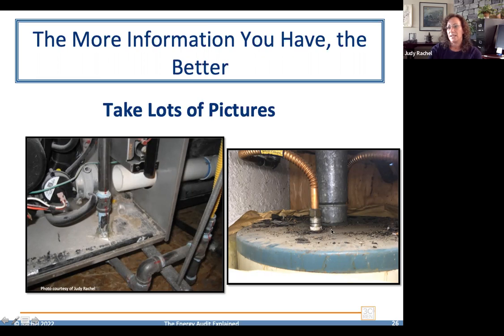And now we've just basically got a great big gas leak going on because we've got this water heater that is firing with no fire. So there's just gas, and it's never going to satisfy because it's never going to heat up to the point at which the thermocouple says, oh, we're hot enough, we're satisfied. So that gas is just going to continue to leak, which will deprive people of oxygen if, say, it's in a garage, or a kitchen or a hallway, or it can explode. So kind of a big deal.